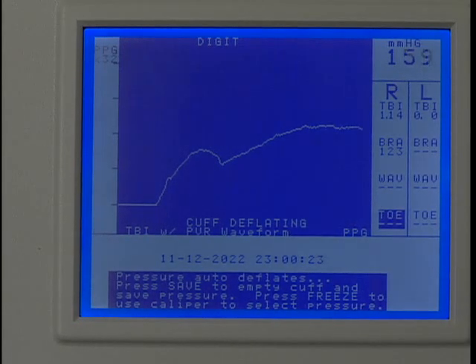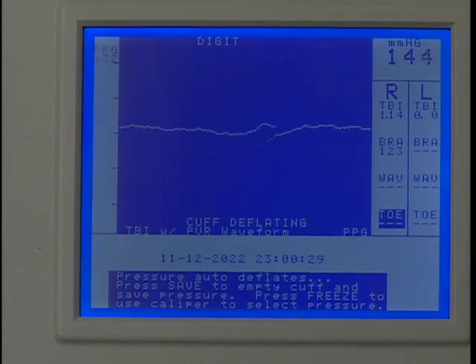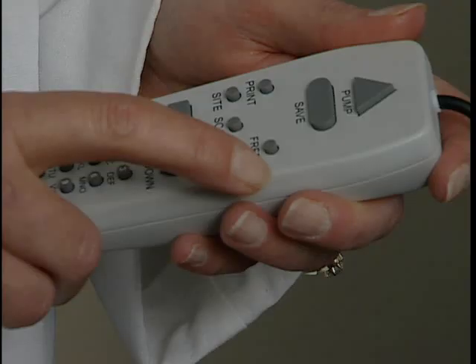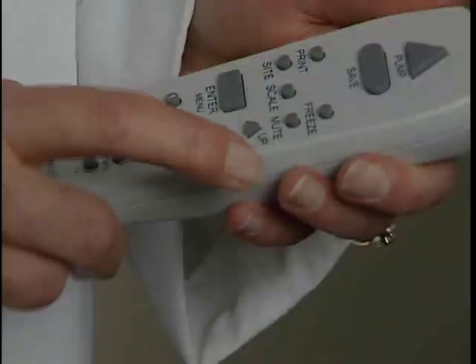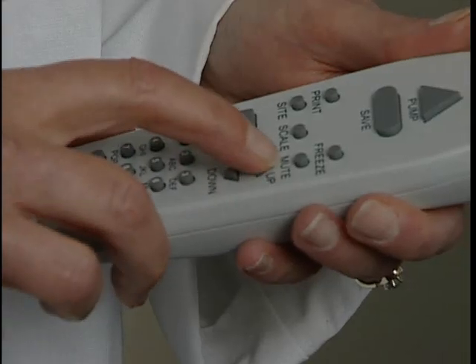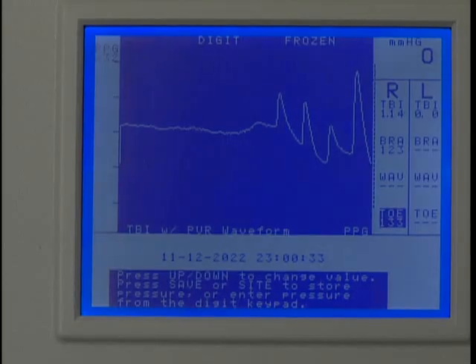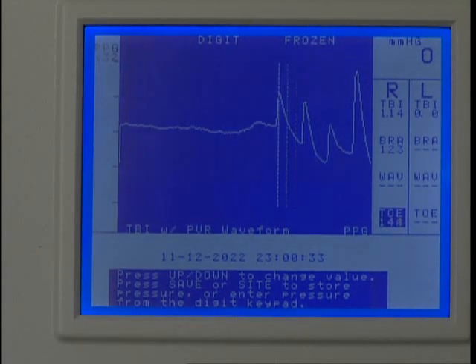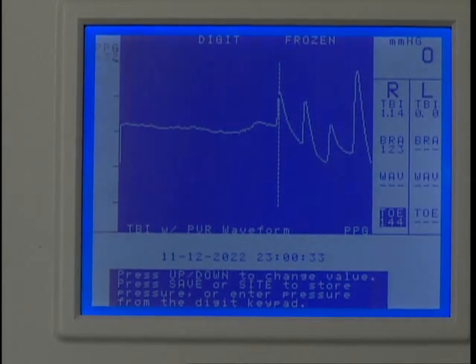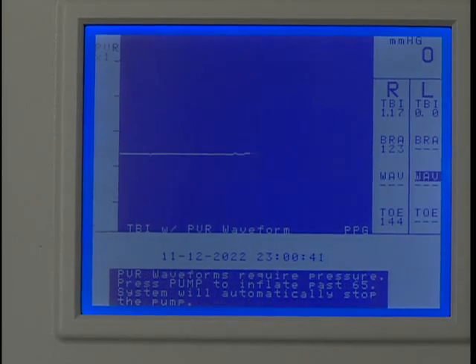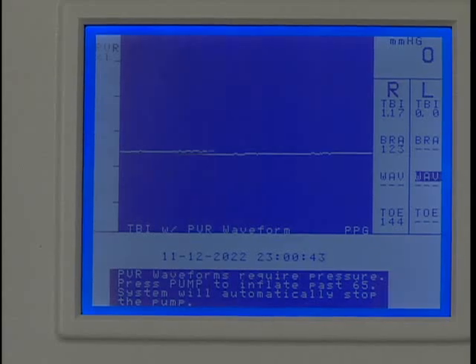The digit cuff will begin to deflate automatically once the pump stops. Press Freeze after several pulses have reappeared. Press the up or down key to move the caliper tool to the beginning of the first upward slope at the start of the pulsation, as shown. This is the systolic pressure. Press Save to record the pressure, and the marker will move to the next protocol location.